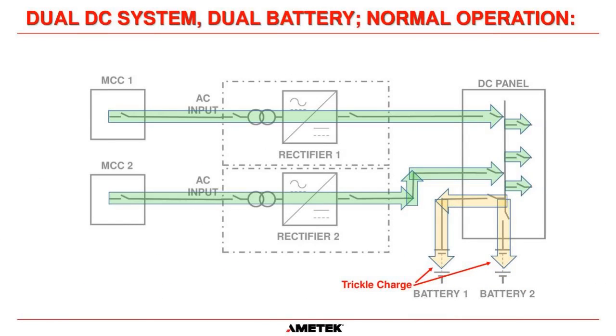Now, in the best case scenario, when you have a dual redundant charger and two batteries, both chargers are connected in parallel. The AC will be converted into DC, and then the DC gets combined on the DC bus within the DC panel. So they are in parallel, and both chargers will be supplying power out to your load circuits. And this brings up a contentious issue. Most people say that the chargers should share the load. I go into this later on.